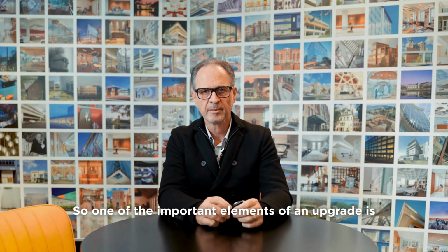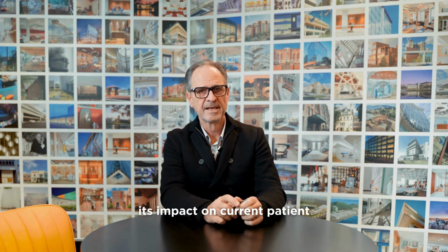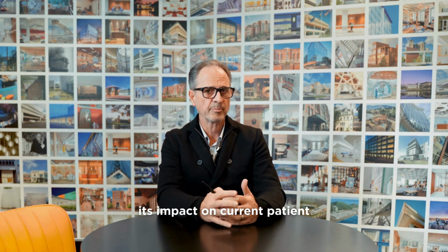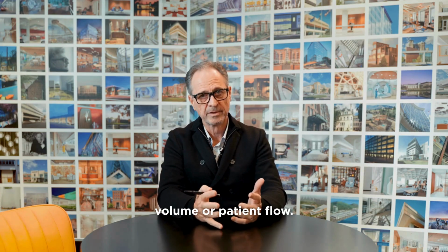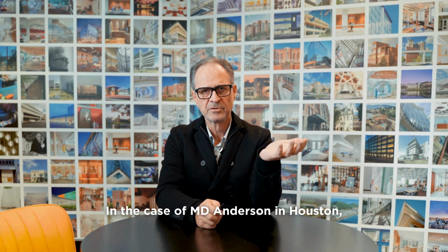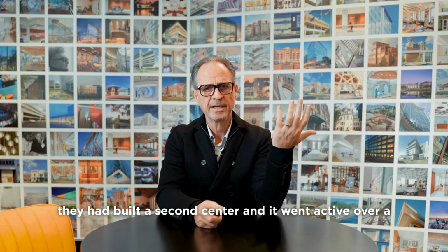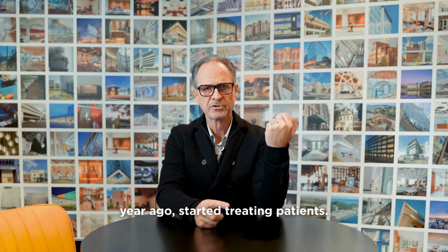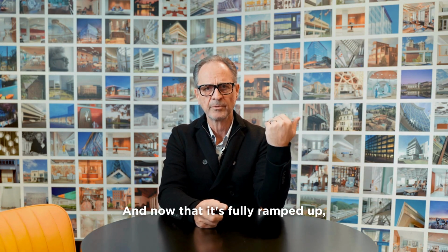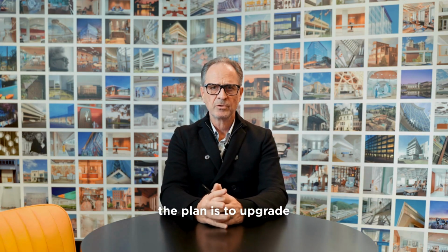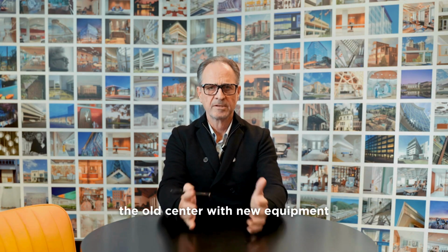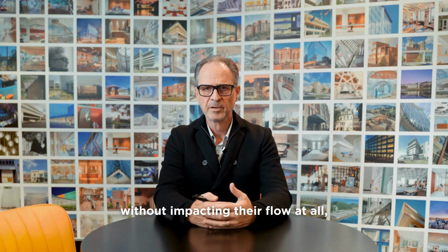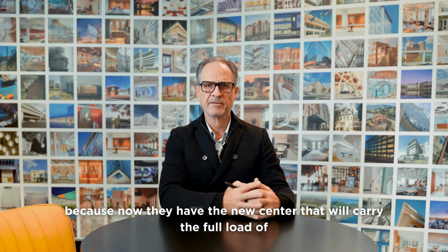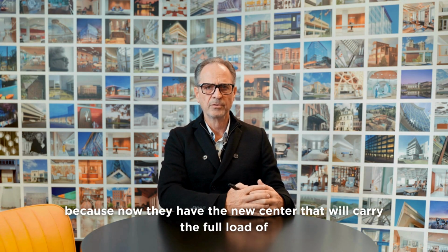So one of the important elements of an upgrade is its impact on current patient volume or patient flow. In the case of MD Anderson in Houston, they had built a second center and it went active over a year ago, started treating patients. And now that it's fully ramped up, the plan is to upgrade the old center with new equipment without impacting their flow at all, because now they have the new center that will carry the full load of the patient flow.